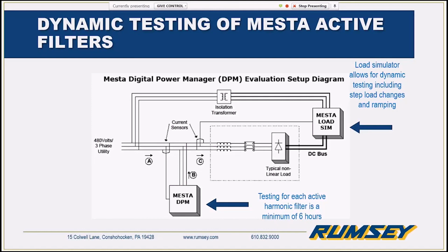Older active filters, part of not being digital, had to use the predictive side of harmonic distortion a lot to try to keep up with the VFD loads, because harmonics are a predictive anomaly if you ramp a drive up from 0 to 100. But oftentimes that's not what was happening in the field. Drives were going up and down and all over, so they would be injecting other current into the line, causing some line instability. So that's something that we make sure we don't do anymore.